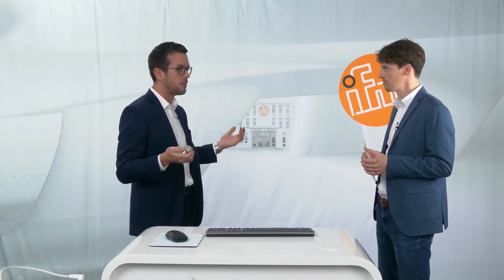In some applications, for example in tooling machines, if you want to detect levels close to tooling machines, you have oil vapor in the air. Even the oil is very aggressive and normally attacks the front part of ultrasonic sensors, and the oil can diffuse into the sensor and destroy it. So the customer might need to exchange the sensor every 6-12 months. With this sensor, you install it and forget about it.